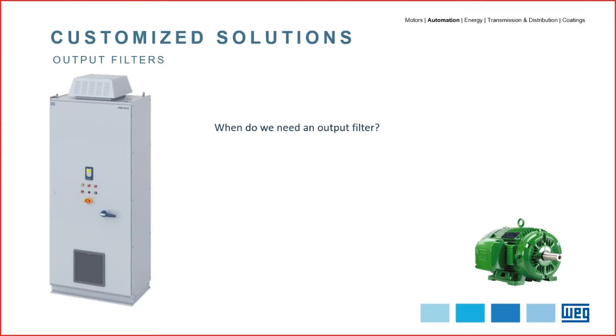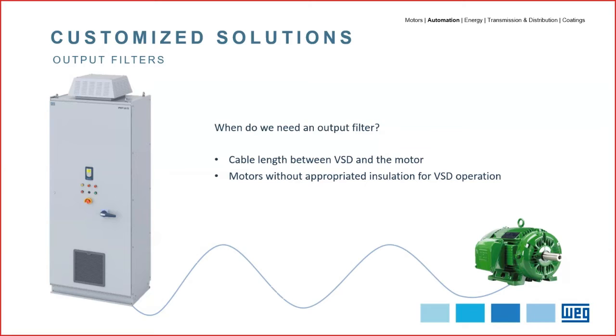So then, every time I start a motor with a VSD, do I need to consider the installation of an output filter? The answer is pretty simple: no. If using a brand new WEG motor and the cable length between the VSD and the motor is less than 100 meters, no additional output filter is required. This is because WEG induction motors are prepared to be controlled by WEG VSDs, so the motor is designed to support the PWM effects without any additional filter. On the other hand, for applications with longer cable length, some additional requirements must be considered.